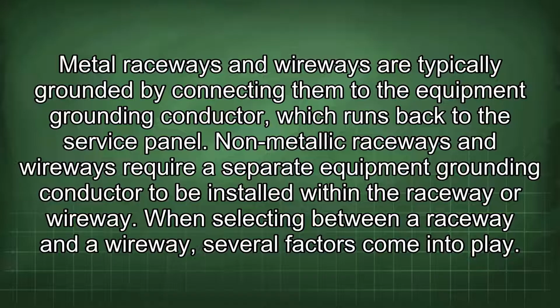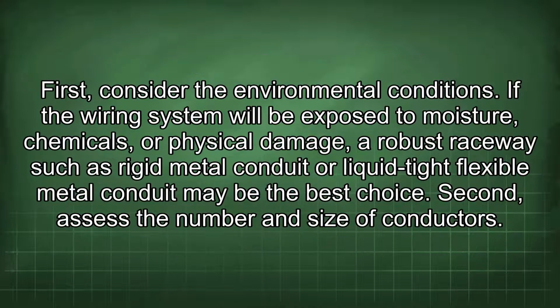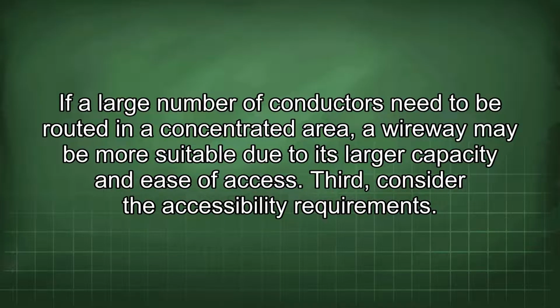When selecting between a raceway and a wireway, several factors come into play. First, consider the environmental conditions. If the wiring system will be exposed to moisture, chemicals, or physical damage, a robust raceway such as rigid metal conduit or liquid-tight flexible metal conduit may be the best choice. Second, assess the number and size of conductors. If a large number of conductors need to be routed in a concentrated area, a wireway may be more suitable due to its larger capacity and ease of access.